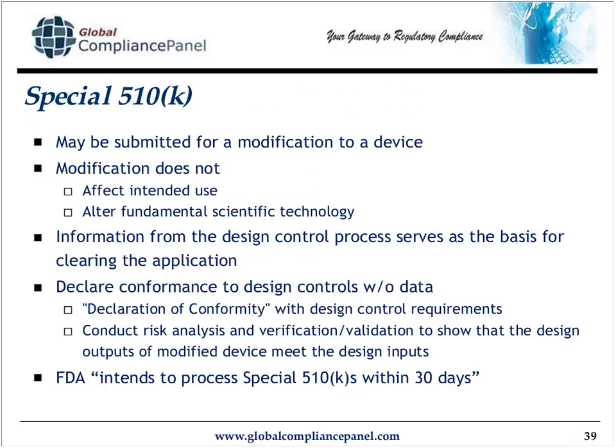A special 510K, as opposed to traditional, is one that you could submit for a modification to a device as long as your modification does not affect the intended use or alter the fundamental scientific technology. This is probably the reason why most of us limit our special 510Ks to product line expansions or new devices that we ourselves are manufacturing. Because how can we possibly know what the fundamental scientific technology of a device is unless we design and or manufacture it? You use the information from your design control process to clear the application.